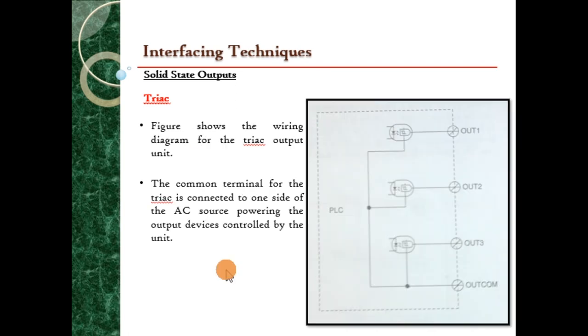This is another example of the wiring diagram for the triac output unit. So the common terminal for the triac is connected to one side of the AC source here that can be controlled by the unit, for example, like the AC power source here. You can see here the triac is using the isolation circuit by using the light beams here. So why is it using the isolation circuit here? Because it wants to isolate the PLC system from the output devices, to control the interfering signal between these two systems that can damage either the PLC or the output devices.